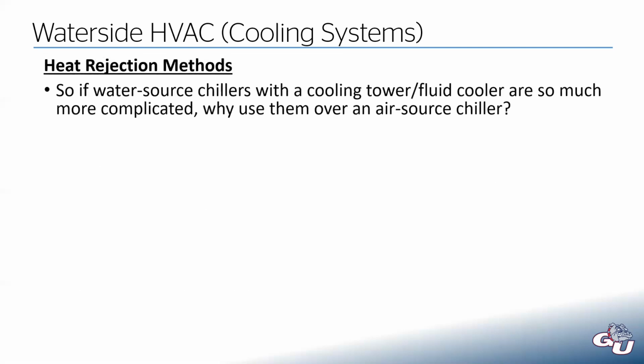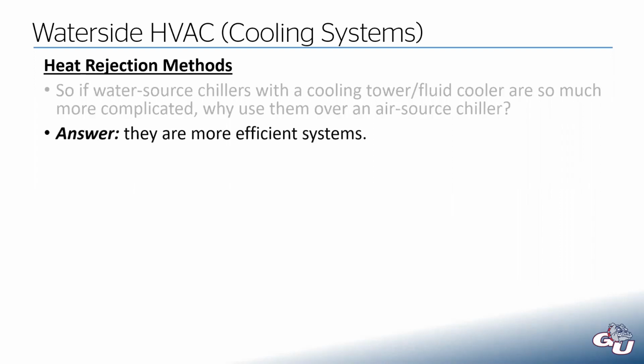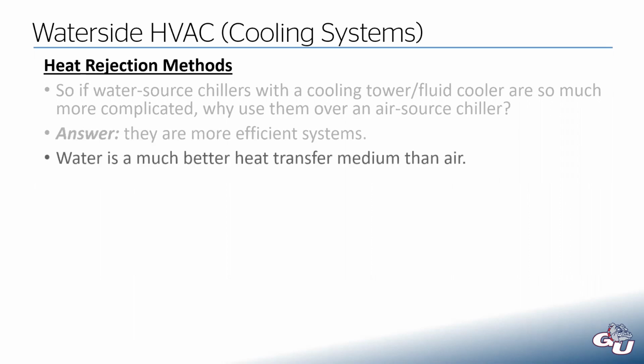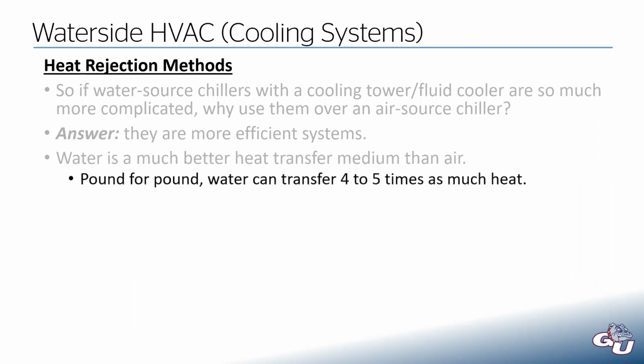So water source chillers with a cooling tower, I mentioned they're so much more complicated. There's all these extra parts and pieces. You have this big cooling tower, you have water treatment you have to worry about, you have more pumps that you have to maintain. Why would we want to use water source chillers instead of an air source chiller? And the answer is they are more efficient systems. Water is a much better heat transfer medium than air.